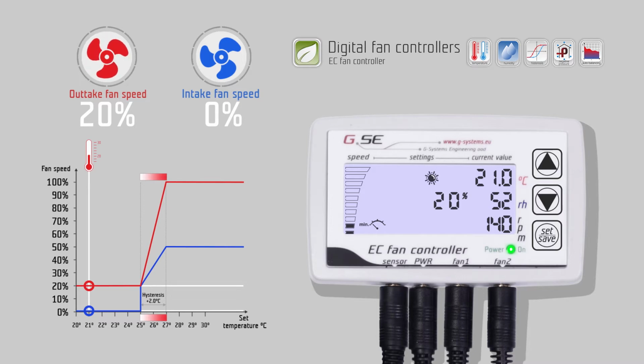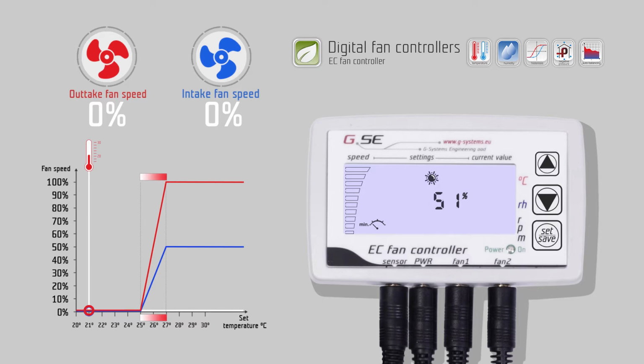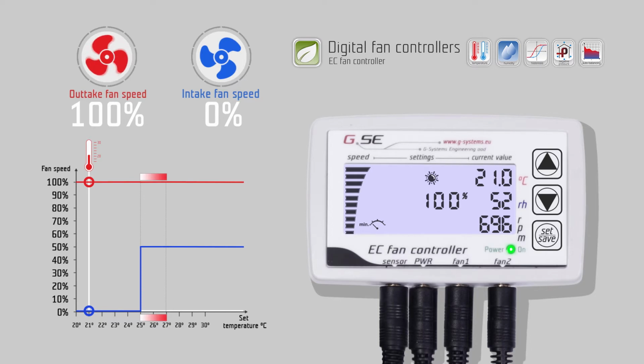The minimum speed setting limits the exhaust fan. It should never be undercut during the regulation. The current minimum speed is displayed on the bottom side of the speed bar. Each filled segment represents 10% fan speed. If the value is set to 0%, the exhaust fan will stop working when the measured temperature or humidity are below their set values. The minimum speed can be set to up to 100% speed. For example, we set the value to 10%.